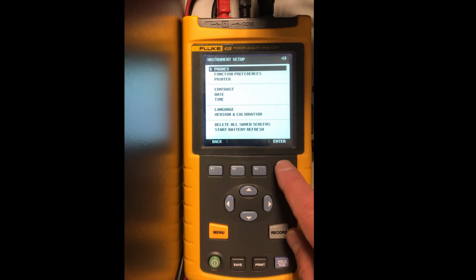On the top it says probes, so I'm going to hit enter there. Notice how probe on number 1 is where we have our voltmeter test leads, and in this case I'm 1-to-1, so I don't need to do any changes. But if I had an attenuator in there that's going to drop the signal by a factor of 10, then I'd have to tell this instrument so that it's going to take that into account and doesn't give me the wrong value for voltage when I measure voltage.